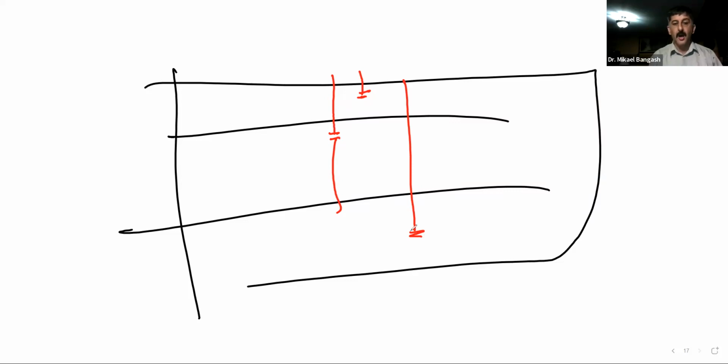You may have no Doppler shift, no blood flow, mainly because the sample window is kept outside the blood vessel. So for you to get a Doppler shift first of all, bring it inside the blood vessel. But if you have it inside the blood vessel and take it to a greater depth, compare this one here as A, and this one here as B. There is a great likelihood that this one here will give you aliasing compared to this one here.